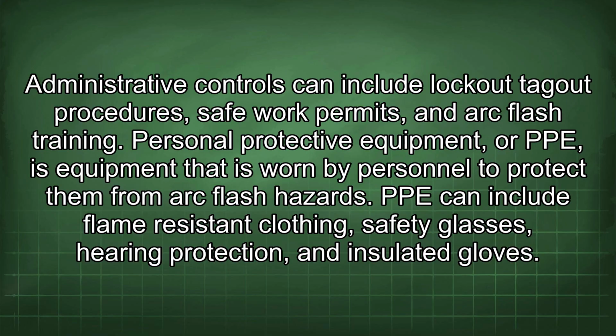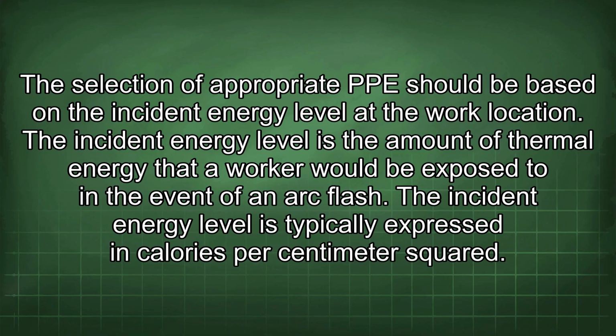Personal protective equipment, or PPE, is equipment that is worn by personnel to protect them from arc flash hazards. PPE can include flame-resistant clothing, safety glasses, hearing protection, and insulated gloves. The selection of appropriate PPE should be based on the incident energy level at the work location. The incident energy level is the amount of thermal energy that a worker would be exposed to in the event of an arc flash. The incident energy level is typically expressed in calories per centimeter squared.